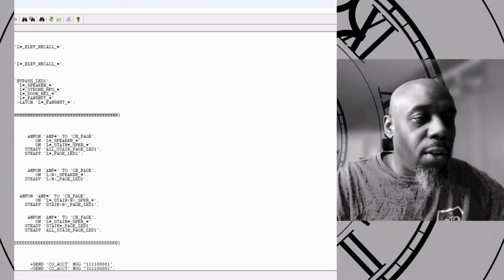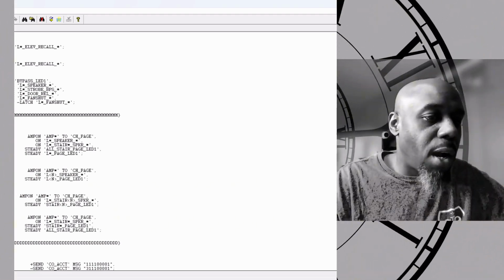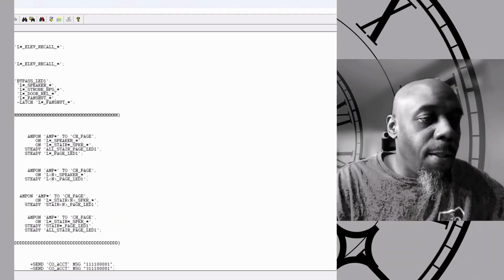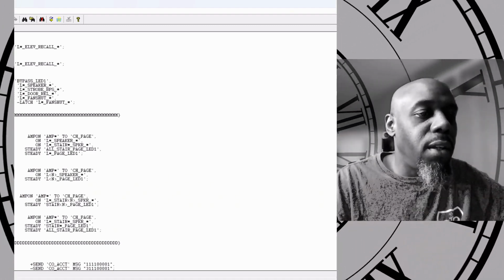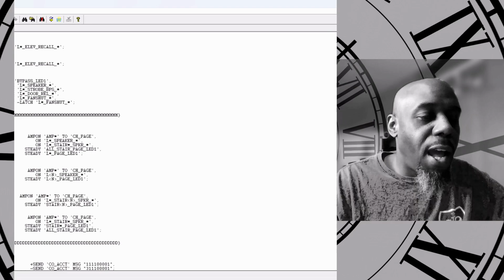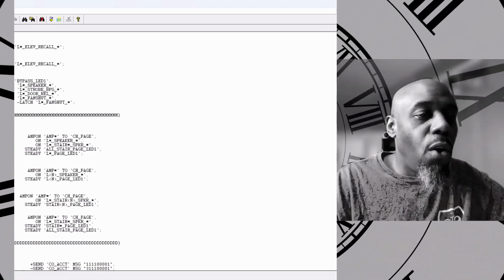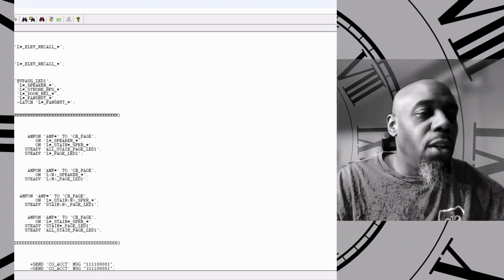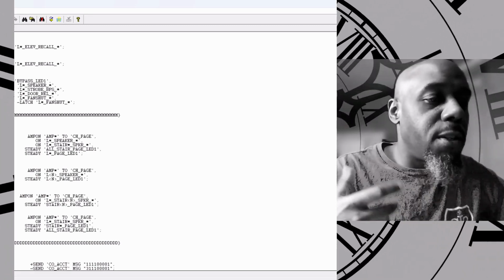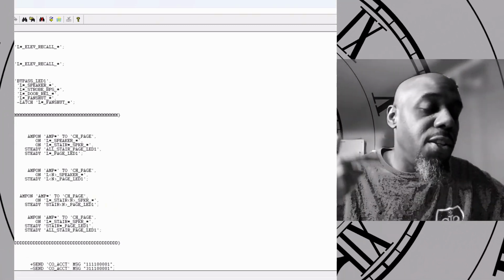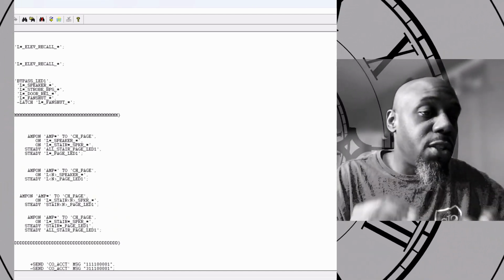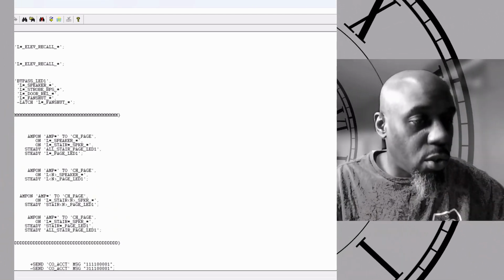We have auto elevator. So this is probably a bunch of smoke detectors. Now there's an I star underscore ELEV underscore RECALL underscore star, and then they have apostrophes. So all of that is relevant. The semicolon, all of this is relevant. So this is the programming language, or these are the syntax that have to be inputted into this rule programming in order for this one particular rule to go true.